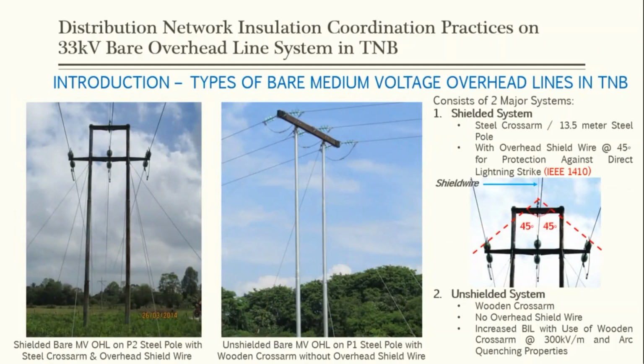And then we also have the shielded bare overhead line system on P2 steel pole, as shown here on the left, and an unshielded bare medium voltage overhead line on a P1 steel pole also with wooden cross arm, and without overhead shield wire. But the design is still having an angle of 45 degree for protection against direct lightning strike.